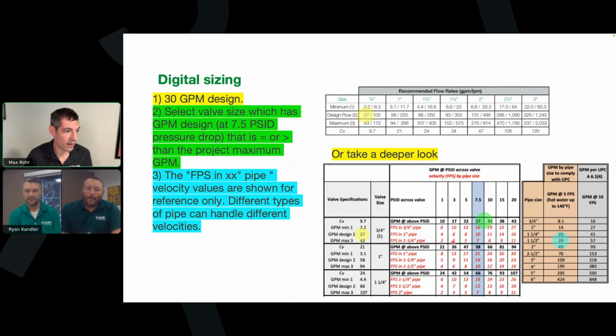Let's say, Ryan, that they said, I'm going with 1.25 inches. Would that valve ever open more than 5%? No, that valve's going to stay basically as close to hot, as small on hot, I should say, and it won't open fully. So what you can see happening is it getting lined up or gunked up with it not always opening and exercising, basically. So we've got a couple issues there, but we're still covered if we went with 1.25 inches at a 4.4 GPM minimum if we said our number was 5. So we're still hitting the minimum flow rate, which is good. So it's not going to be hunting.